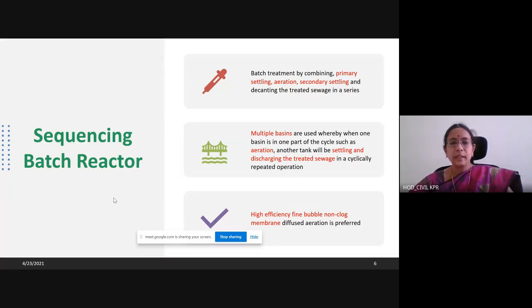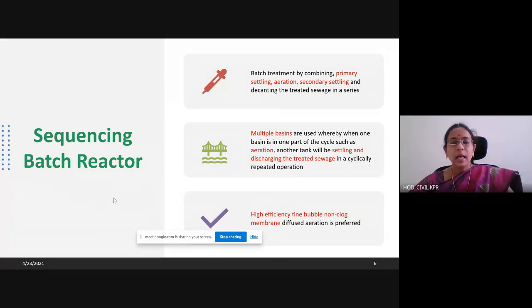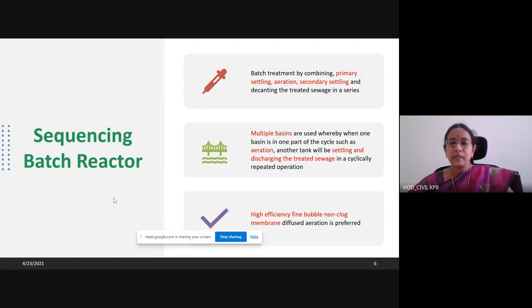Multiple batches can also be placed depending on the characteristics of the wastewater. It is a cyclic process: it starts with primary settling, then goes to aeration, then to settling, and if required, it is sent to a second cycle where the same process is carried out. Settled particles are taken out for disposal and the remaining water is taken out for use. Multiple basins are used — when one basin is in the aeration phase, another tank will be in settling or discharge. All these tanks can also be put together in a single tank. This combined three-treatment process is called a batch reactor. A Sequencing Batch Reactor means one after another in a sequence, happening inside a separate unit.